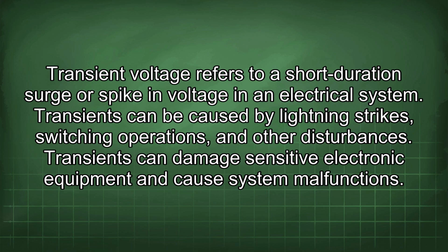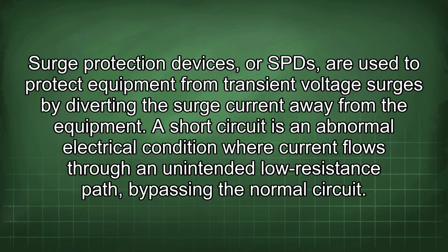Transient voltage refers to a short-duration surge or spike in voltage in an electrical system. Transients can be caused by lightning strikes, switching operations, and other disturbances. Transients can damage sensitive electronic equipment and cause system malfunctions. Surge protection devices, or SPDs, are used to protect equipment from transient voltage surges by diverting the surge current away from the equipment.